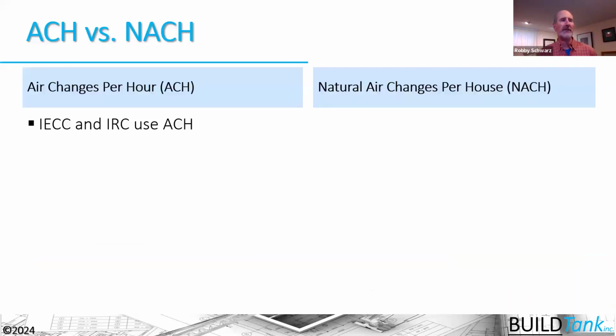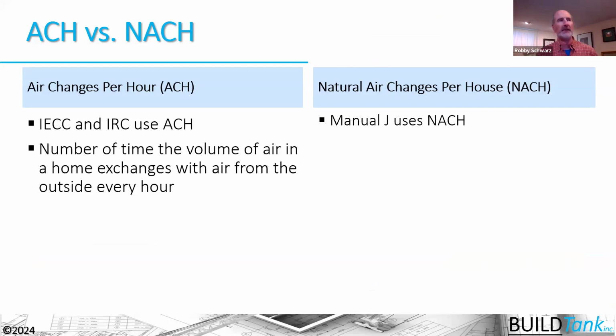So air change per hour is what the IECC and the IRC use to measure air leakage. Manual J actually uses natural air changes, or NACH, rather than air changes per hour, or ACH. So air changes per hour is the number of times the volume of air in a home exchanges with air from the outside every hour. So when we have a code requirement that it's at 3 air changes per hour, it means that the volume of air inside that house exchanges with air from the outside 3 times every hour.